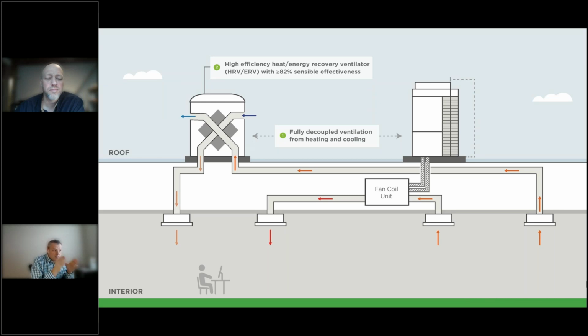This separating and using the HRV, ERV is critical in decreasing the runtime and energy consumption of the heating and cooling system. So the next piece is pairing up the high efficient ERV, HRV with a very high performance heat pump system.